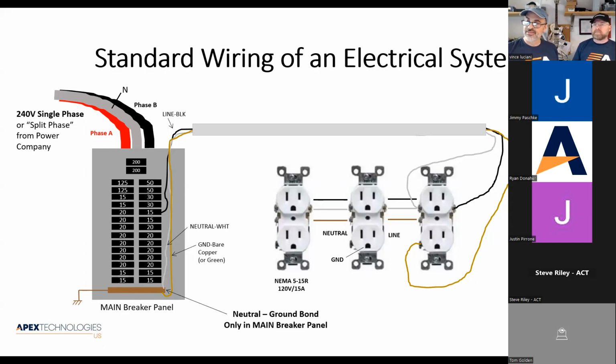It's really just a path so that if the system should get hit by lightning, there is a path for that lightning to go. What's interesting to note is that neutral and ground get terminated to that same bar, right? So the intention is that neutral and ground are connected together. And if you have a voltmeter and you test the voltage between two points that are connected together, you get 0 volts, right? They're shorted together. So the intention is neutral and ground should be 0 volts. We'll get to that later, probably tomorrow, when we talk about isolation transformers and why they're good. But remember, neutral and ground are intended to be connected together.